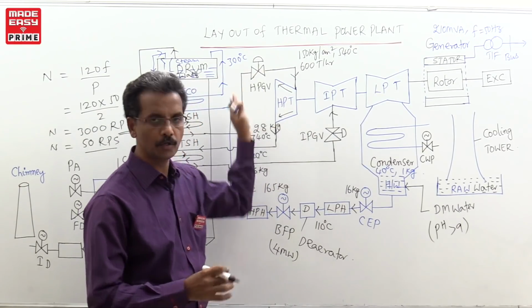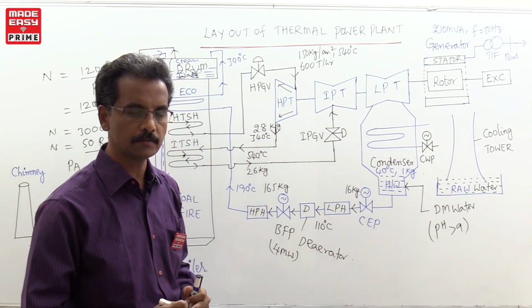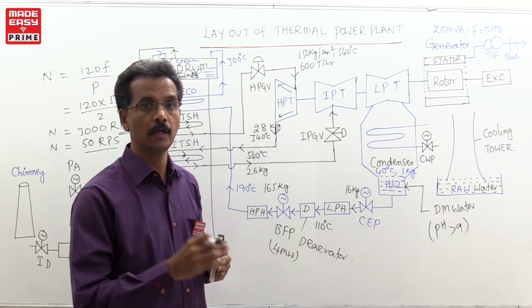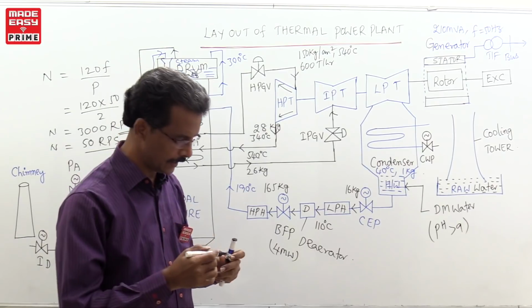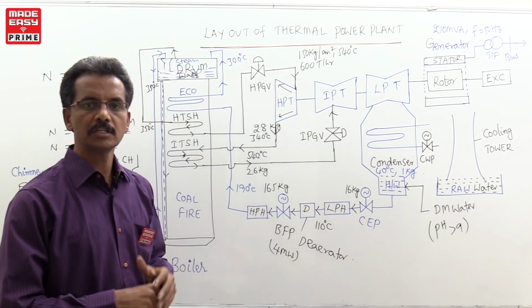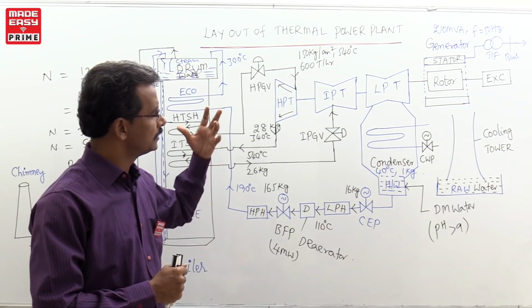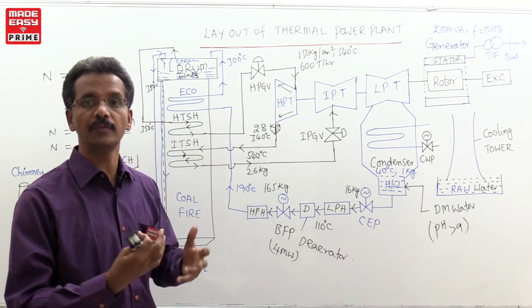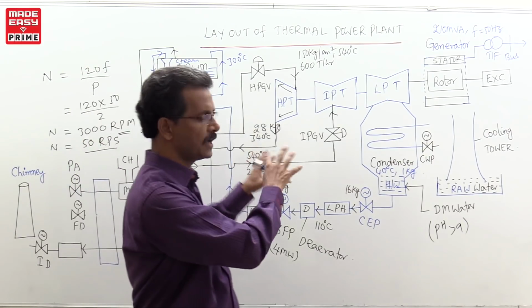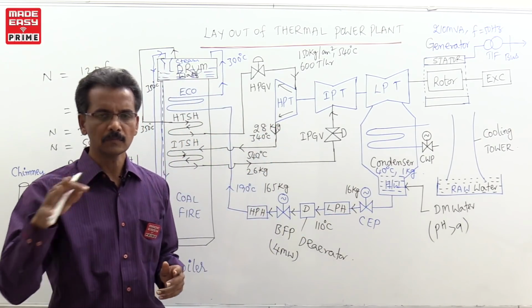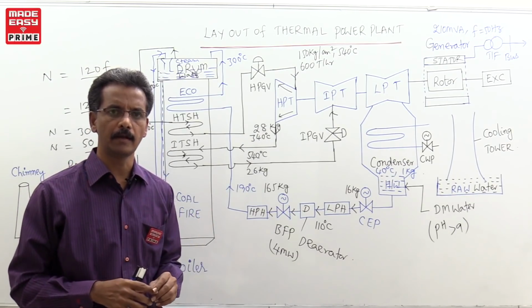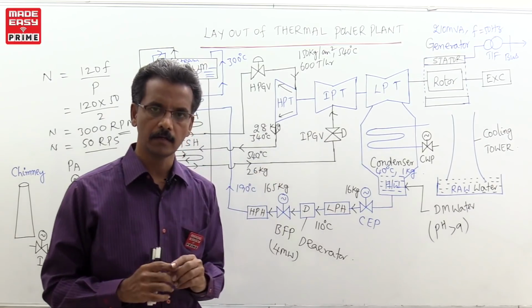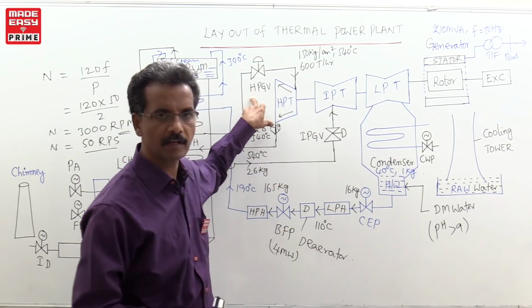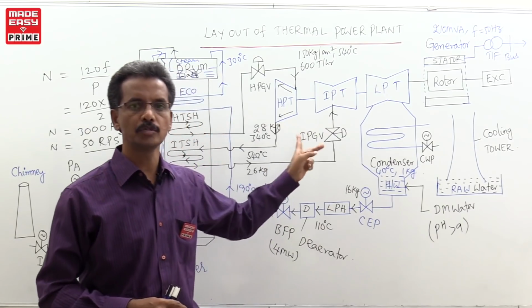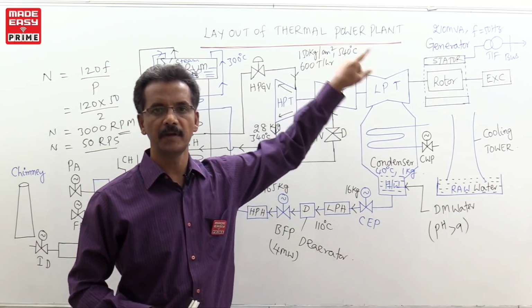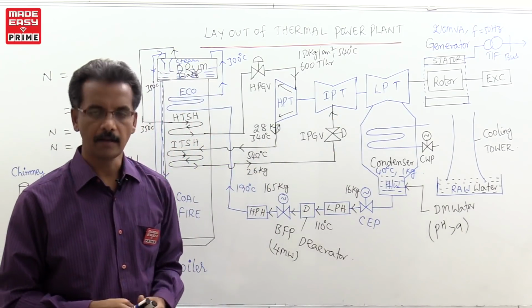So, these two governing valves are used to control the steam flow rate, and thereby the speed of the turbine. This is also one more important point for electrical engineers: how to control the speed of our turbines, or, another way they will ask, how to control the frequency. In my regular class I do all these diagrams with animation, showing diagrammatically how the governing valve looks. The HP governing valve and IP governing valve are mainly used for controlling the speed of the turbine and the generator, which will indirectly affect the frequency.